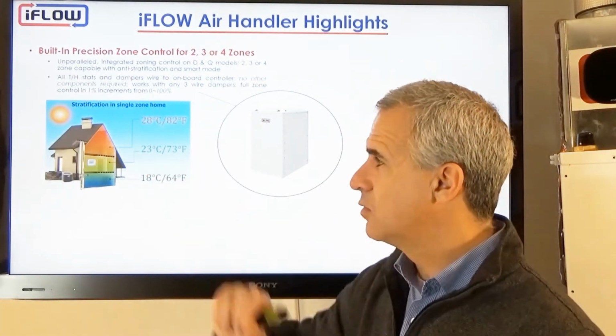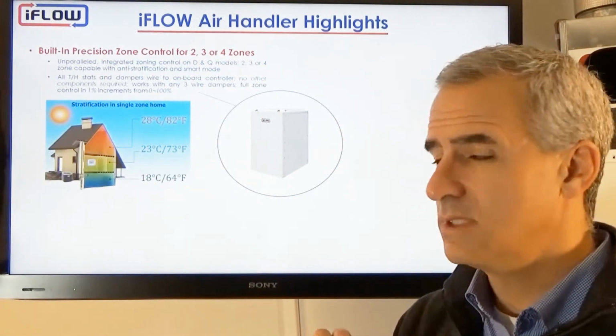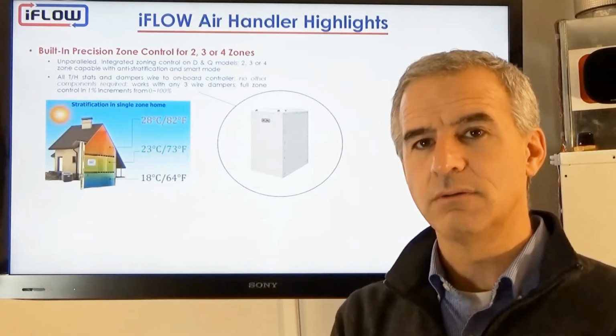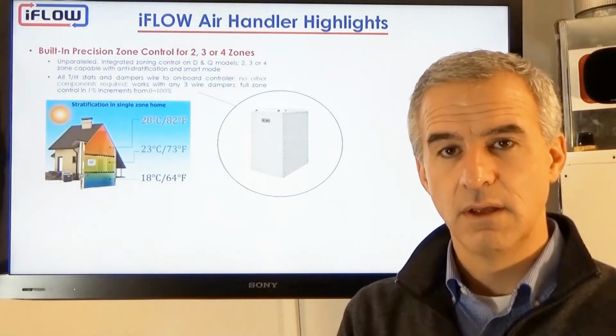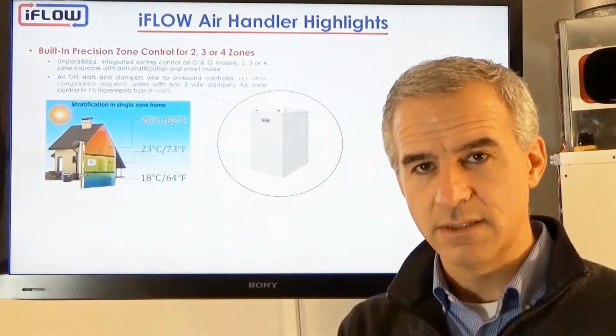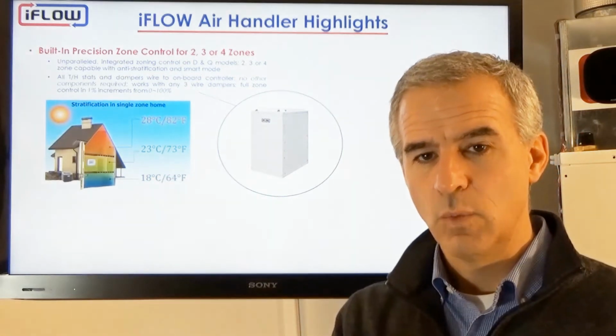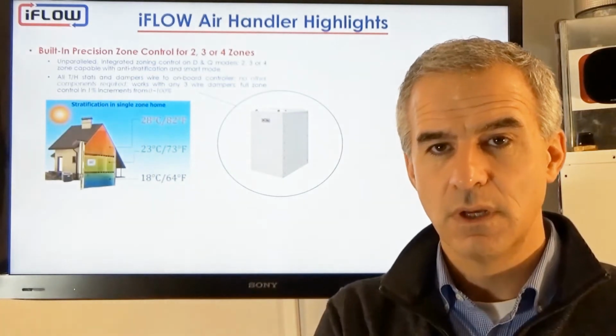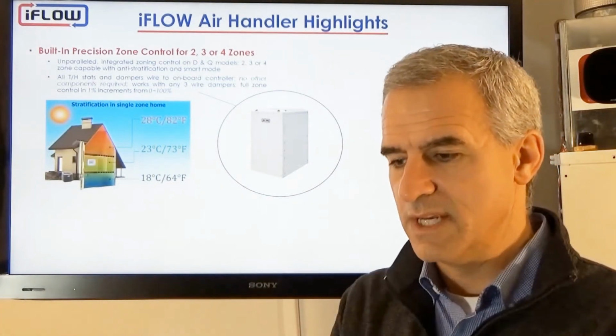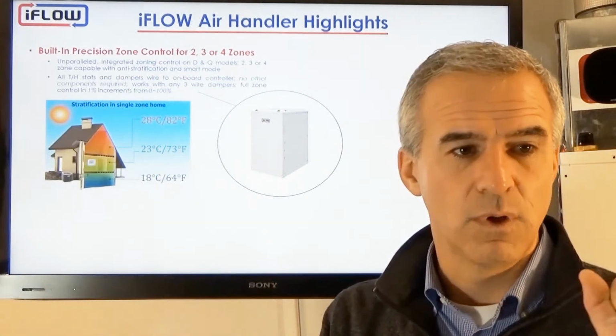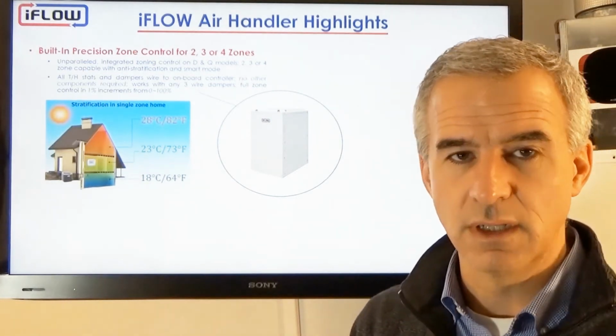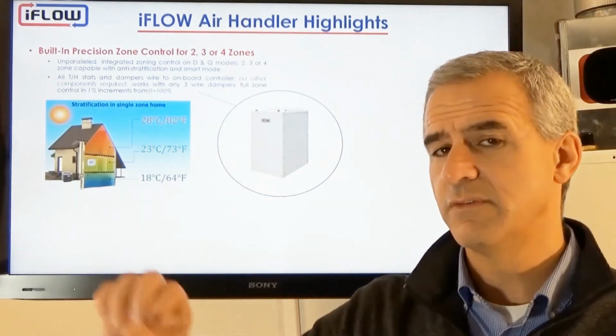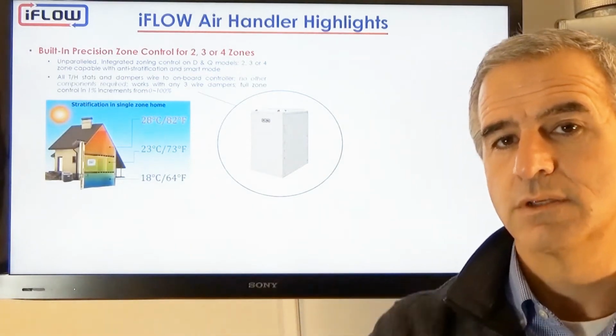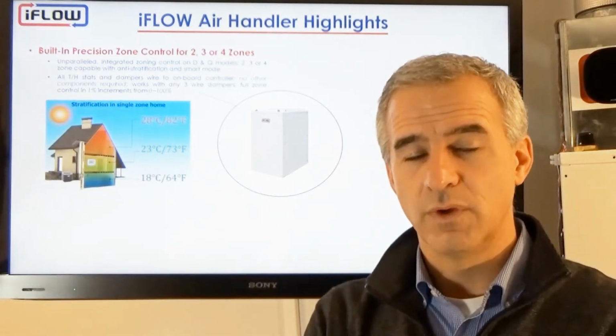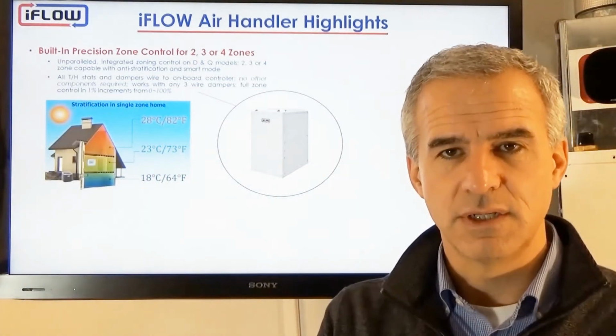In terms of that zone control, we'll be able to deliver that same modulation that we have on the whole house side, that 0 to 100% in 1% increments. We can now apply that to each of the zones as well. So we can divvy up the zones as best in your house, and then say if one zone needs 35%, we can deliver 35%. If another zone needs 50%, we can deliver 50%. So we can tailor each zone with that same modulation capability.